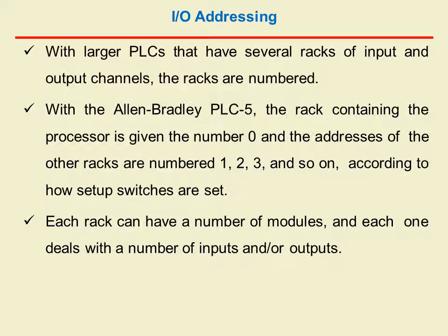With larger PLCs that have several racks of input and output channels, the racks are numbered. With Allen Bradley PLC 5, the rack containing the processor is given the number 0 and the other racks are numbered 1, 2, 3 and so on.